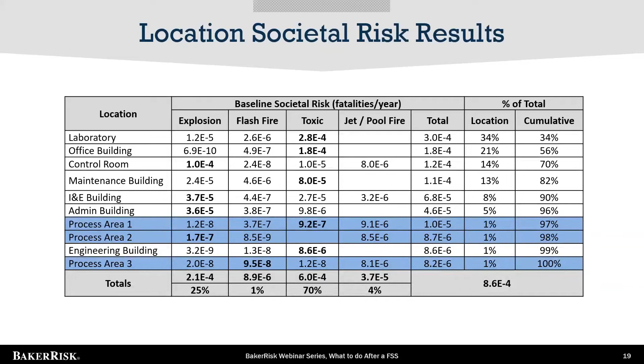Looking at potential mitigation options for the laboratory, office, and maintenance buildings driven by toxic hazards, I would look at what the current emergency response strategy is. Is it evacuation or shelter in place, and should it be changed? If it is shelter in place, how is the HVAC system isolated and how leak tight is it? Could we make the isolation system more reliable? If it was manual, could we make it automatic? Could we add detection and automatic shutdown of the HVAC system? Could we improve the leak tightness of those buildings?